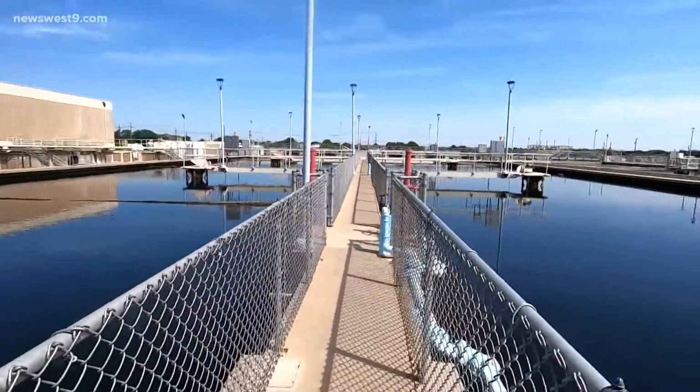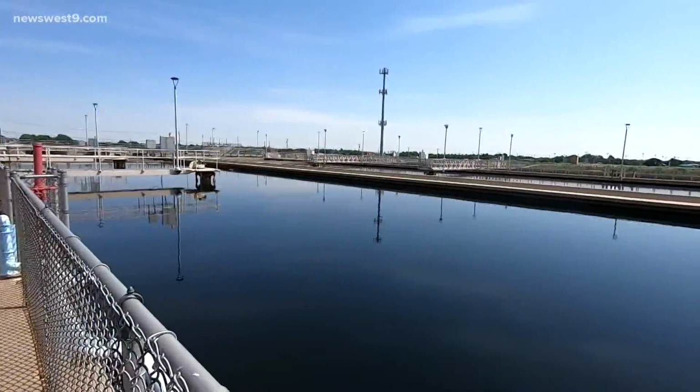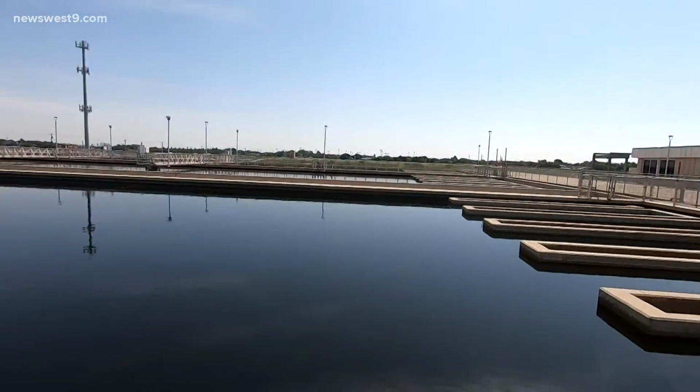But you might still have some yellowness to your water here and there as the city treats it. It's normally around July or August. Sometimes we get a little bit of a yellow tint in our water, and that's manganese that has gotten into the system as we are starting our treatment cycle. It's harmless. It's a secondary contaminant, meaning it changes the color of the water, but it's harmless to the human. But no one wants to shower in yellow water. Nobody wants yellow water. Yes, that's true. Or to drink yellow water. So that is what the sodium permanganate and the potassium permanganate is for.